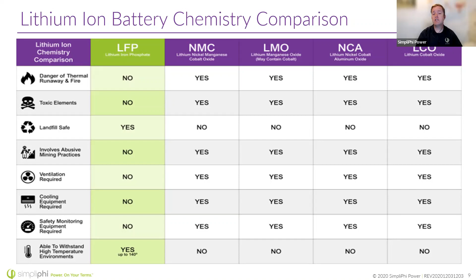And here's why: if you're relying on a piece of cooling equipment to keep the battery in spec and that piece of cooling equipment fails, well, the battery fails. So these are other modes of failure that cause systems to fail. And so if we can remove those, we're increasing the reliability of the system. I'll go into it here in a minute, but we're able to work in some really extreme high temperature, low temperature environments.